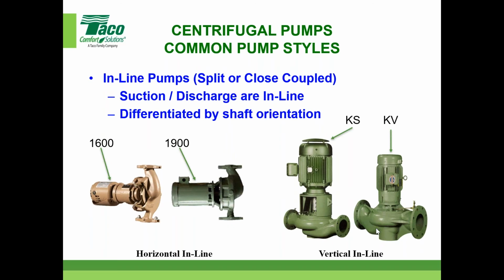Just because one is closed coupled and one is split coupled doesn't mean it changes performance, as long as the numbers are the same—the model number, horsepower, impeller cut, and all the internals—you're still going to get the same flow and head out of it. So on the left side is the split coupled, and I'm going to show you some other pictures.